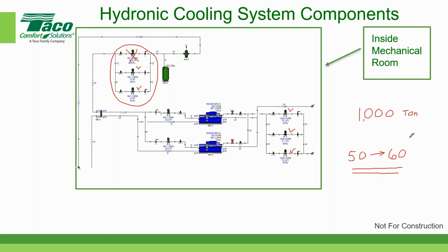It requires that the primary flow have a minimum flow. So in other words, if you specify a chiller, in this case we're specifying two chillers at 500 tons each, that chiller may only have a 60% turndown. Each chiller requires about 1,000 GPM on the chilled water side and about 1,500 GPM on the condenser water side. Well, if it's variable primary flow on the chilled water side, and that chiller can only withstand 60% reduction in flow, that's limiting. You can only turn down your flow to 60%. So if we had a 1,000 ton system, we had 2,000 GPM, like we've been talking about, 2 GPM per ton, 60% of that for one chiller would be 600 gallons per minute.